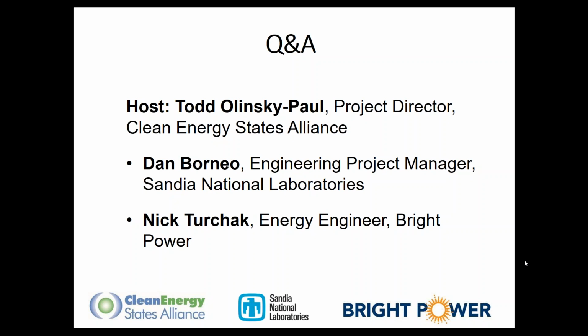Yes, I would second Dan on that. There are several interesting technological solutions in the advanced lead acid space. You are able to see lead acid batteries now that can be discharged almost up to 60%, meaning minimum is at 40% state of charge, and up to 4,000 or 5,000 cycles. But those batteries with carbon and capacitance are primarily very low voltage, so you need to install a lot of them. Also, I would note the zinc-based chemistries. Those could be either flow batteries or packaged batteries, and they are typically also on par with vanadium redox 4-hour batteries.